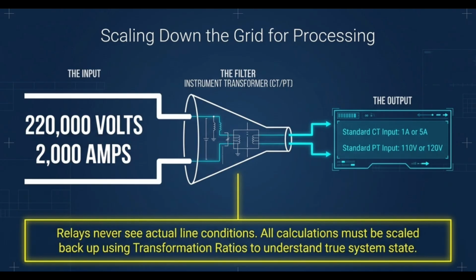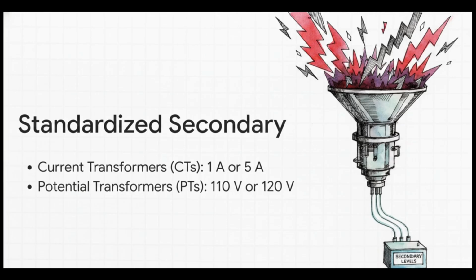So what do those whispers actually sound like? Well, these translators consistently convert the chaotic energy of the primary lines into neat, standardized secondary levels. For current transformers, or CTs, that safe whisper is standardized at either 1 amp or 5 amps. For potential transformers, or PTs, the secondary voltage is stepped down to 110 or 120 volts line to line. This feeds the relay perfectly digestible, safe data.